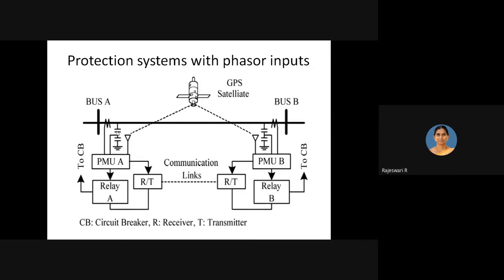As far as differential protection of our transmission lines is concerned, it is an effective way to solve the protection problems of transmission lines equipped with series compensation and FACTS devices. Due to the need to ensure synchronization of input signals at both ends of the protected transmission line, true differential protection was not possible before applying synchronized phasor measurement.